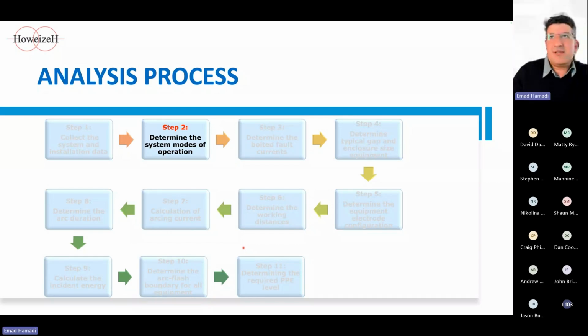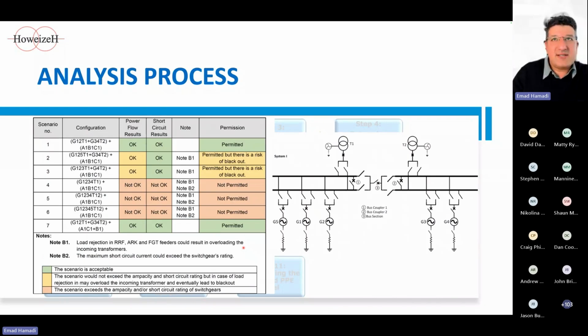Okay, I think I lost track of the time a bit, so going through that. This is just an example of a project that we worked on, during which, in the assessment of the operational scenarios, we found some network configurations that could practically lead to a fault level exceeding the switchgear rating. This highlights the importance of considering every possible mode of operation. The point is, unless you conduct this study, you would never know about such issues. And the arc flash study provides valuable insight into how your system can behave in the case of a fault.